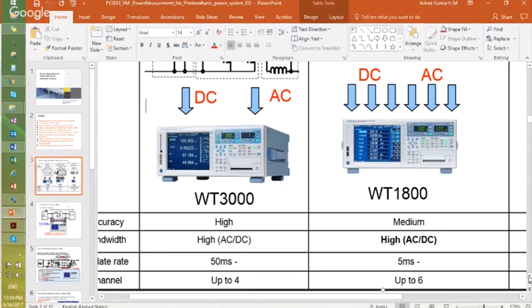No, sir. The reason is precise measurement—at the same moment the instrument cannot go to the first and second in parallel. It's a matter of timing. When you use 2 equipments, both will work at different times. We may not visibly see the different timings, but the crystal frequency or internal clock working in one equipment is totally different from the other. When you're calculating efficiency, if the timing is not good, you won't get exact or good efficiency. That is the reason the equipment is available with 6 channels—so one equipment can calculate input and output at the same time, working with the same frequency, and the resultant will be exactly the same.